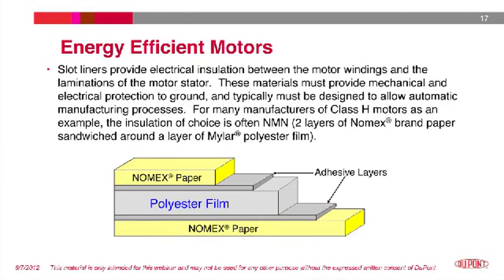To provide a further increment of improved performance, we looked at what could be done to improve the slot liner to allow a more corona-resistant material, which would still meet the requirements of the application. Slot liners are designed to provide electrical insulation between the windings and the laminations of the motor stator. The main requirements of a slot liner are stiffness for automatic insertion, high tear strength to prevent mechanical puncture from the sharp edges of the stator lamination stacks, good dielectric properties depending on the voltage class of the motor, and finally, to be capable of handling the short and long-term thermal requirement of the motor design.